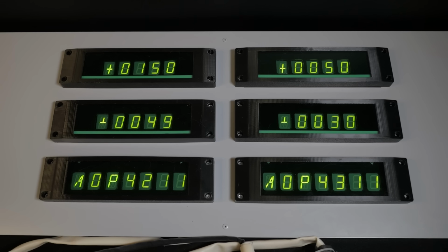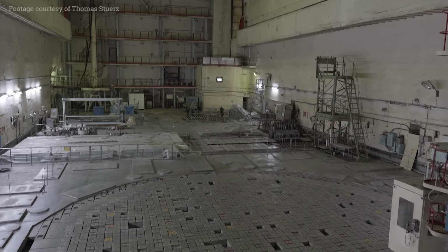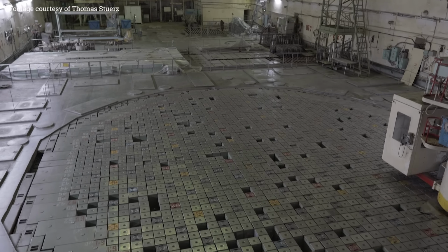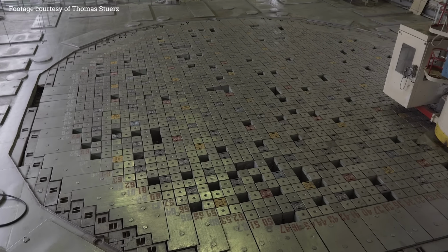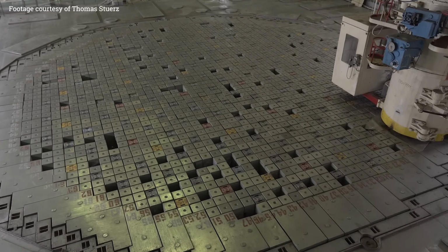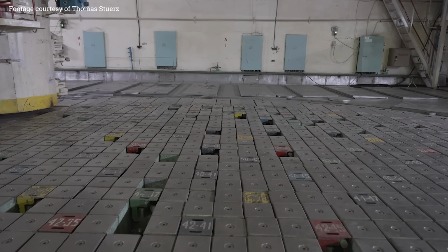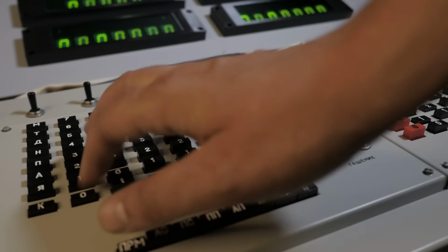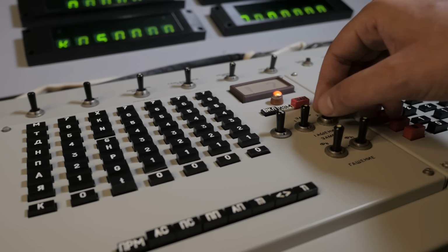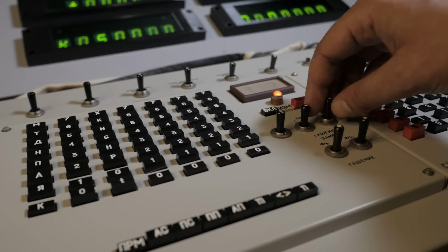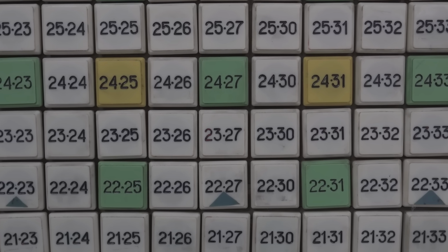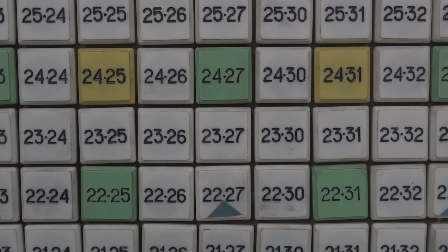But everything we have looked at so far have been so-called parameters of individual monitoring. This is where SKALA can do even more interesting things, because it can also work with channel-by-channel data. An RBMK reactor contains almost 2000 channels. Most of them contain nuclear fuel. Others contain control and protection rods, instrumentation or other systems. So using this console, you can retrieve a huge number of parameters for them, either for all channels at once or for one specific channel you are interested in. You choose it using its octal coordinates. These are those numbers written inside the squares. All channel-by-channel request codes begin with the letter K.